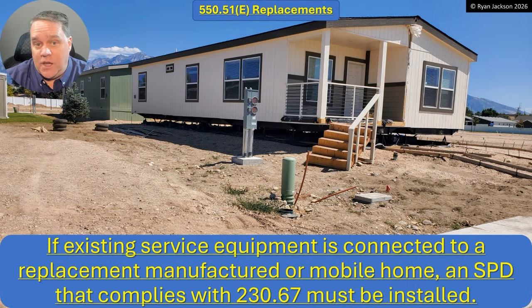And for an installation like this, that would definitely be the case. So 230.67 already applies, right? And 230.67 says if you do a service change, if you change the service equipment, you have to provide surge protection. But usually at a manufactured home park like this one, you're not doing service changes, right?